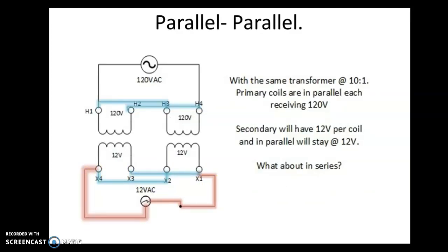In a parallel parallel transformer configuration, you would see full voltage applied to each coil. That means the primary, each coil is only rated to handle 120 volts, which is exactly what we're applying to it. So at 10 to 1, each coil can handle 120 volts on the primary and 12 volts per coil on the secondary.